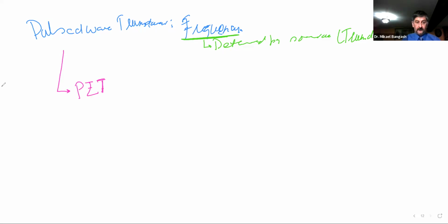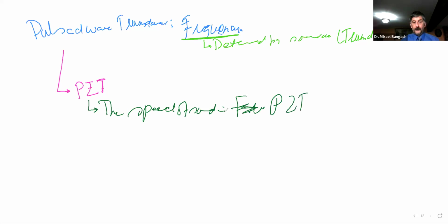So there are going to be some features of your PZT within the transducer that will determine the frequency. And the first one is going to be the speed of sound in the PZT, or your piezoelectrical material. Did that make sense? So that's going to be one of the factors. How does that make sense?